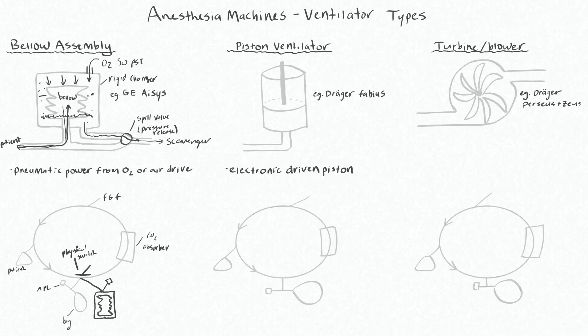If you get used to looking at the bellows and assessing how much air is in your circuit, you may be disappointed to use a piston ventilator where you don't get that same visual feedback. This piston ventilator is just an electronically driven piston that goes up and down, and this chamber will fill with air and then get sent out to the patient. This piston will not collapse if there's insufficient air in the circuit.